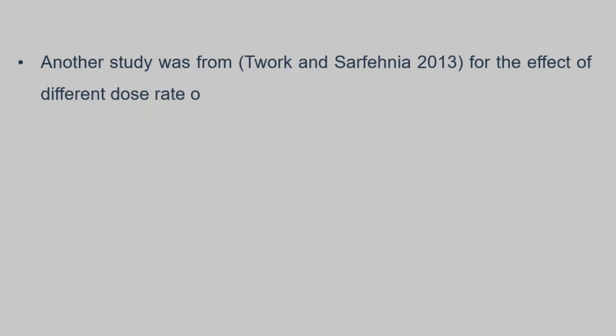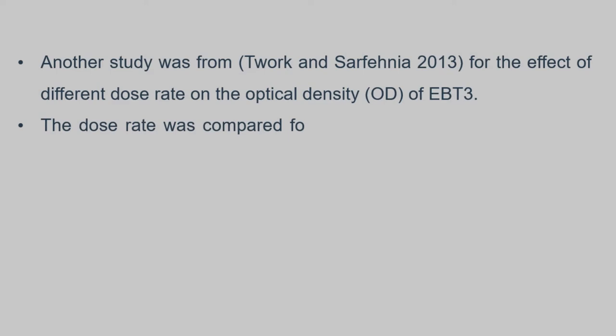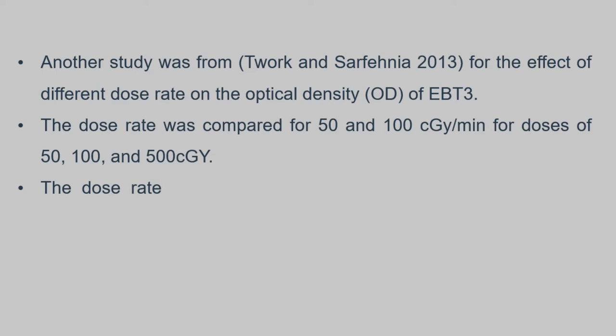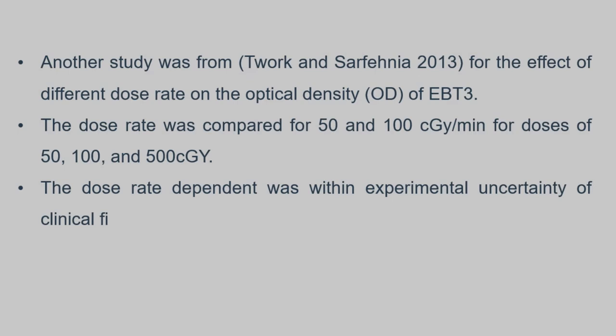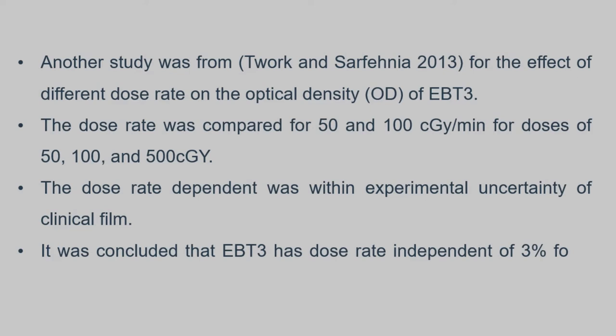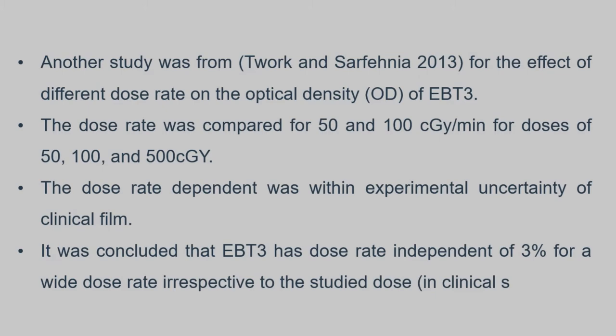Another study from Twork and Sarfehnia in 2013 examined the effect of different dose rates on the optical density of EBT3. Dose rates were compared at 50 and 100 cGy per minute for doses of 50, 100 and 500 cGy. The dose rate dependence was within experimental uncertainty of clinical film. It was concluded that EBT3 has dose rate independence of 3% for a wide dose rate respective to the study dose.